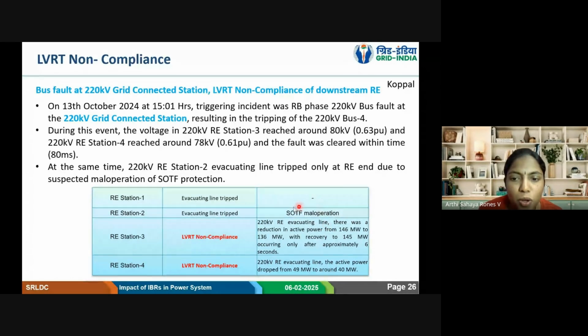I hope all of you might have heard about this SOTF function. The requirement of this SOTF function is like this: let us say some line has tripped and we are attempting to charge the line. At the time of charging the line itself, let us say there was a fault. Whenever we charge the line, we charge first from one end, then the other end. Preferably if generating station and substation are there, from the substation end only we close it. Also, we see the voltage conditions at the remote end, whether it's a long line or short line, whether the line reactor or bus reactor is to be taken in service, like that. So when we charge a line and if there is a fault in the line, we don't have to wait for zone 1, zone 2, zone 3 and all to pick up.